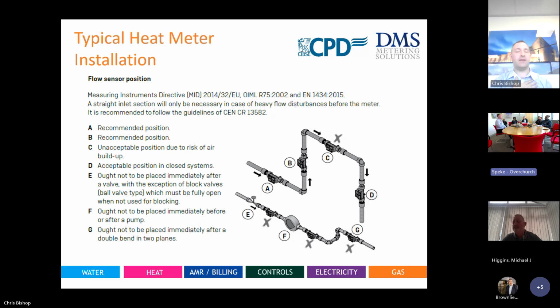So we just state very basically: return installation, unless otherwise stated. Because we can have that conversation where a meter is installed in the flow, and might be completely away from the pump itself. But yet again, these installation parameters we have to know, and actually have to program into the meter, to say flow application. That's the main thing to cover for installation.